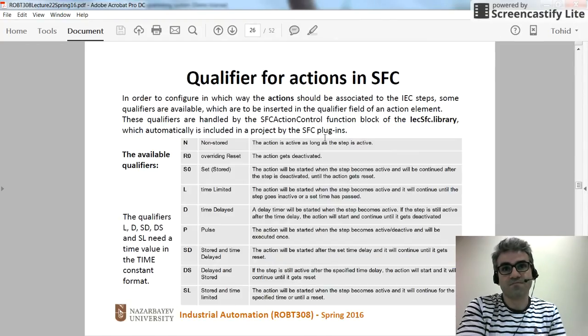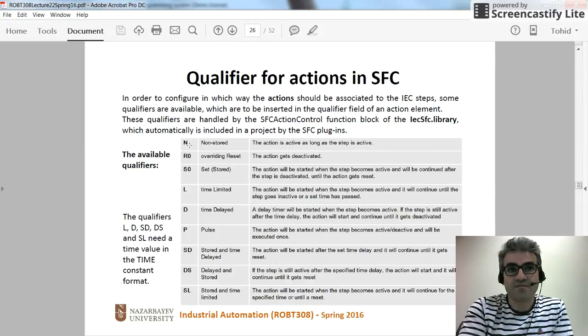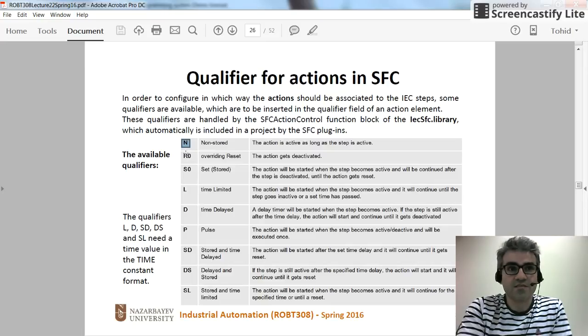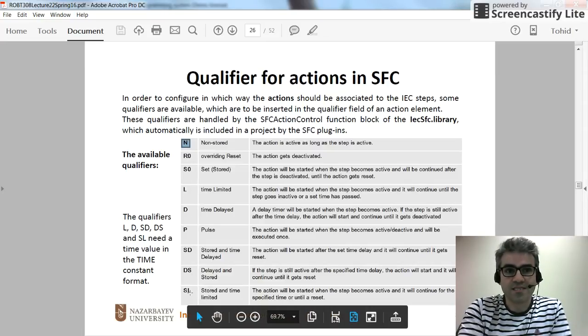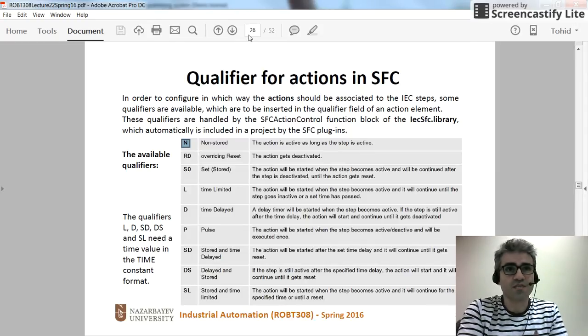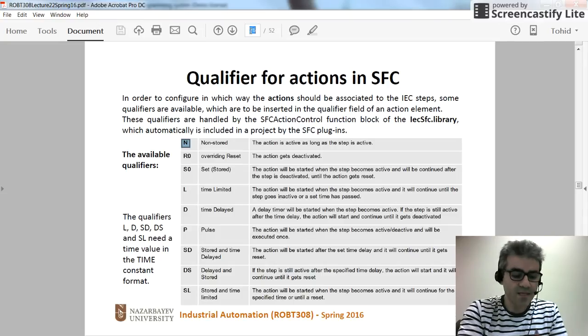We have N, which is not a stored one — in this case the action is active as long as the step is active. The others are R0, S0, L, D, P, SD, DS, and SL. I will maybe explain them later, but for now I'm going to use only the N qualifier and show you the difference.